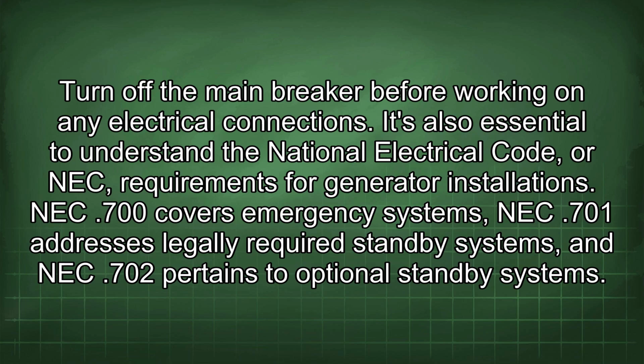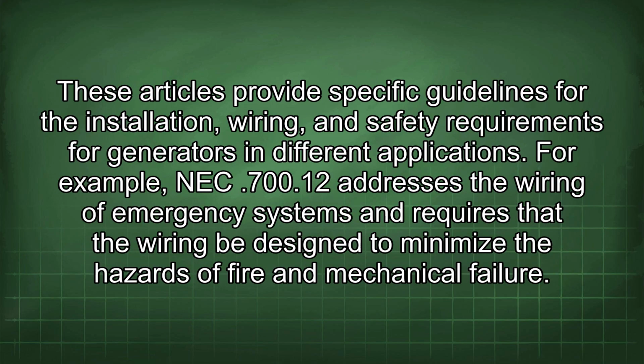NEC 700 covers emergency systems, NEC 701 addresses legally required standby systems, and NEC 702 pertains to optional standby systems. These articles provide specific guidelines for the installation, wiring, and safety requirements for generators in different applications. For example, NEC 700.12 addresses the wiring of emergency systems and requires that the wiring be designed to minimize the hazards of fire and mechanical failure.